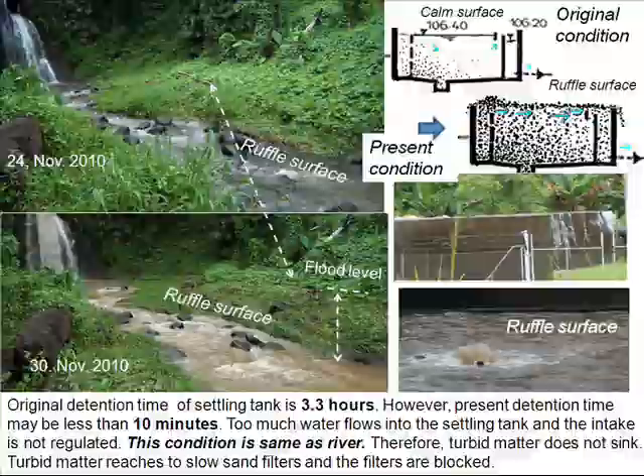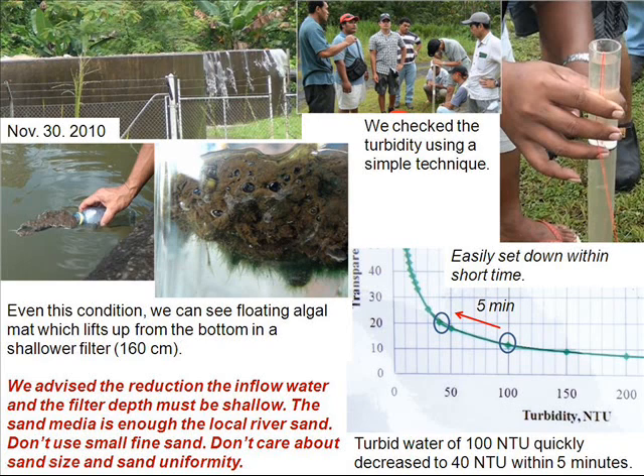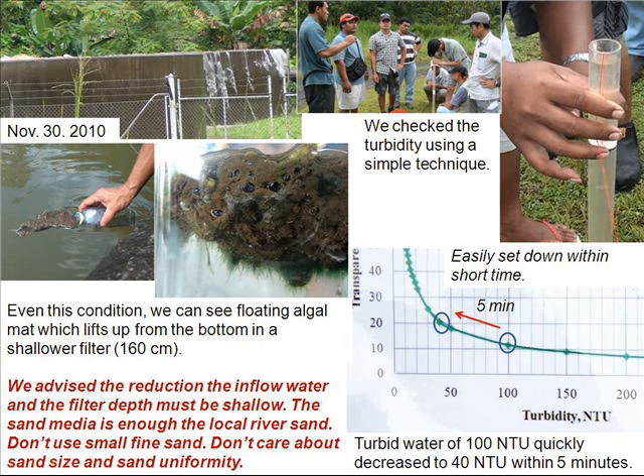After the flooding, they did not control the inflow. We checked the turbidity using a simple technique — just transparency. Turbid water of 100 NTU quickly decreased to 40 NTU within 5 minutes. Even under this condition, we can see floating algal mat lifting up from the bottom in the shallow filter.